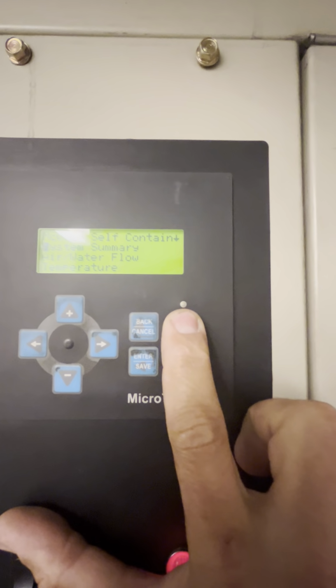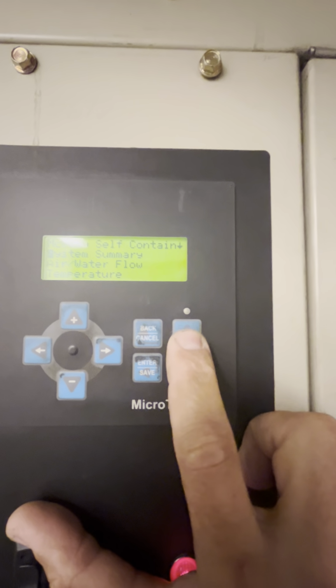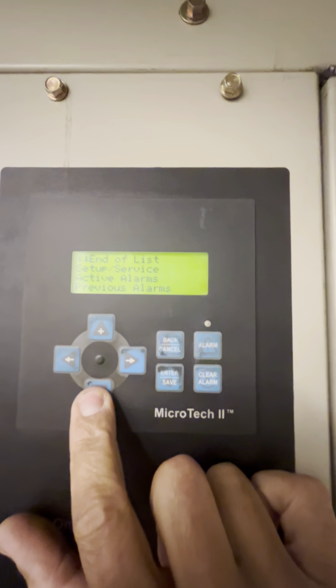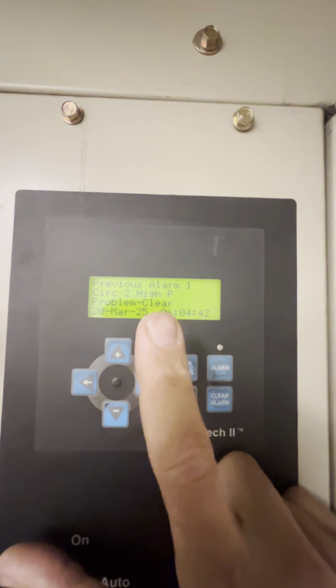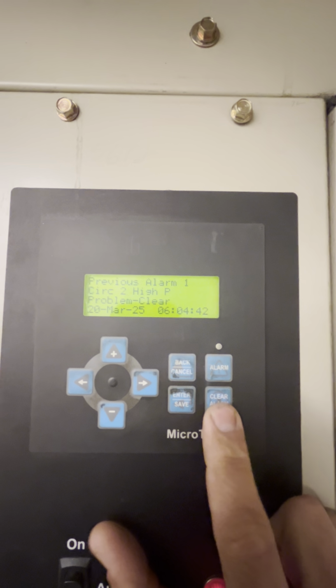If this light was on, that means you have an alarm. We would click that, it would display what the alarm was. Right now it's saying no active alarms. I'll go down to previous alarms so you can see what it would look like if there was an alarm. Right here, previous alarm. So this would populate, then you would just hit clear alarm and it would wipe that away. If the problem persists, then that light would come back on. And then you need to do further troubleshooting. We'll go back to the main screen here.